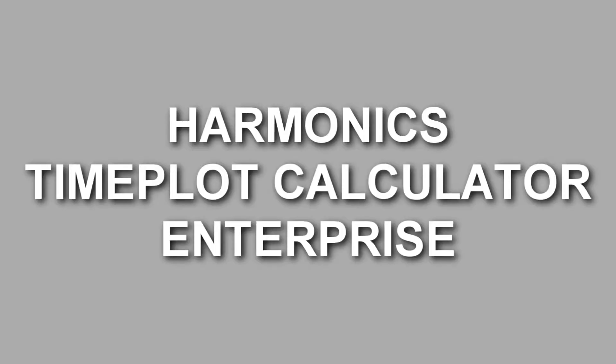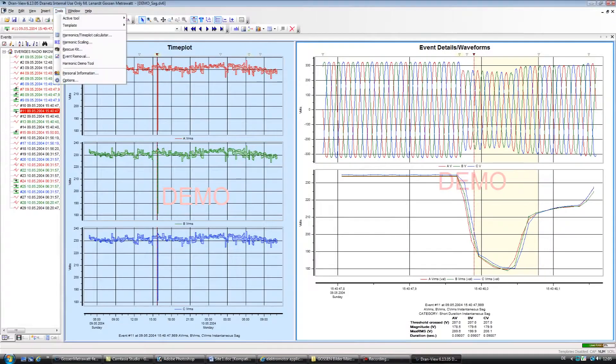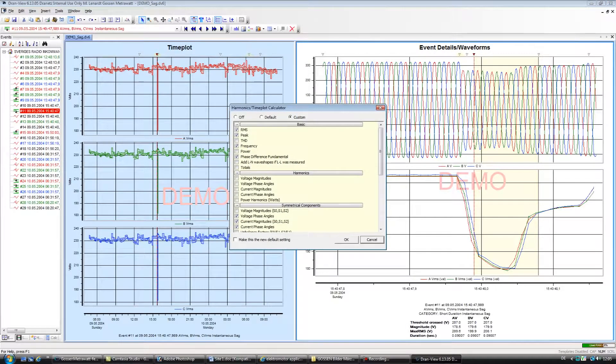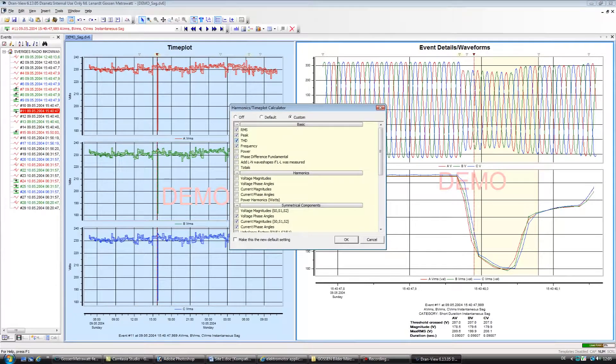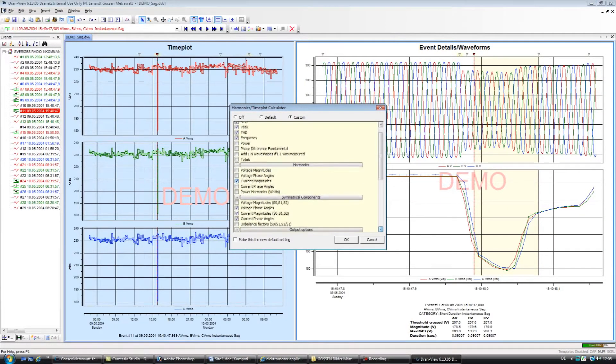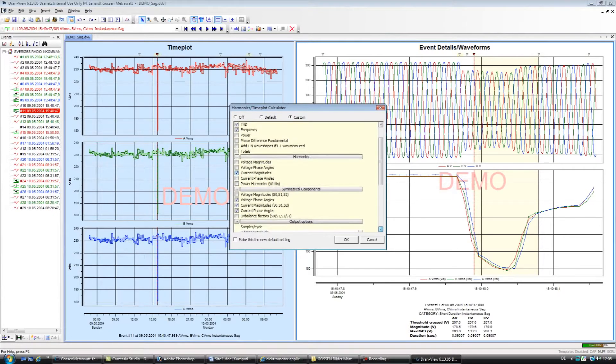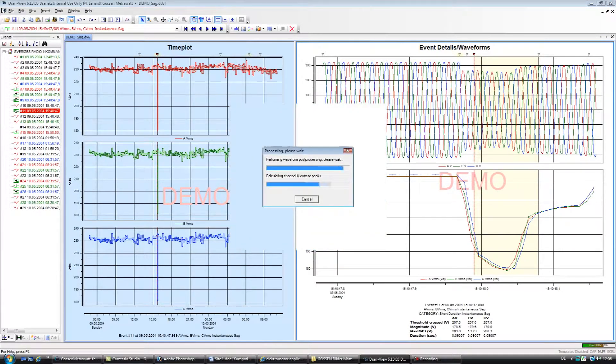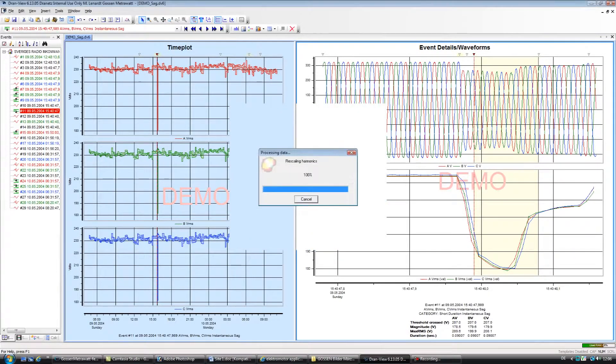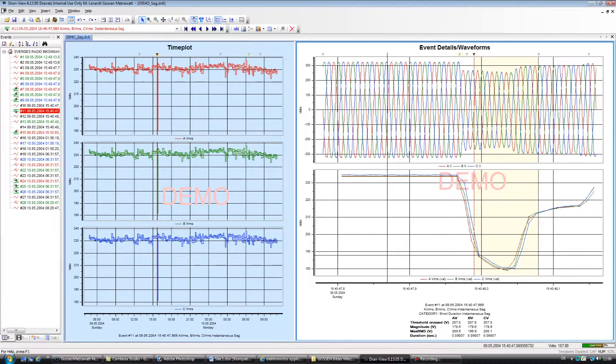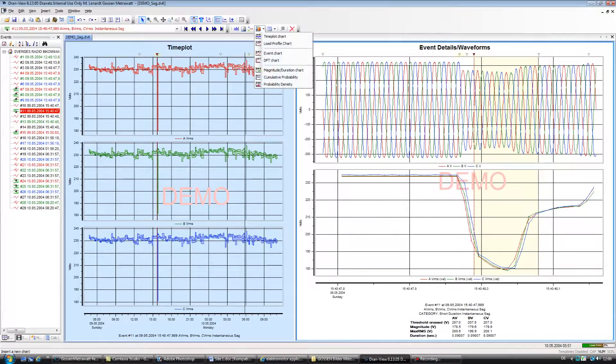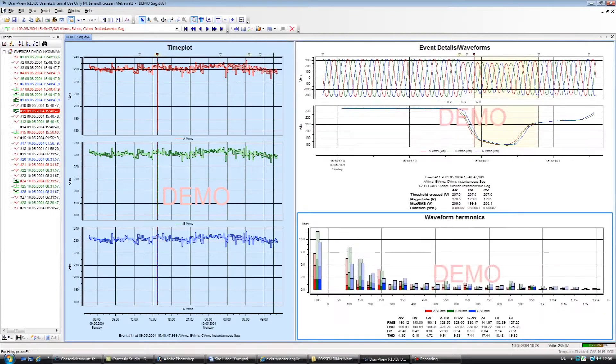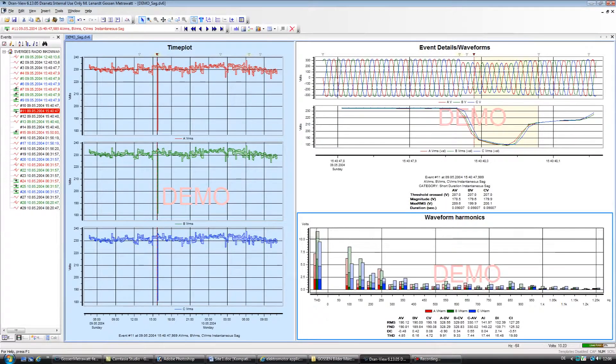Harmonics Time Plot Calculator in Enterprise. Dran-View can also compute RMS, power, harmonic, and other parameters from the wave shape information recorded by the instrument. This is in addition to any parameters recorded directly by the instrument. Dran-View Enterprise can create trends of harmonics and other parameters using the journal wave shapes by using the Calculate Harmonic Time Plots tool.